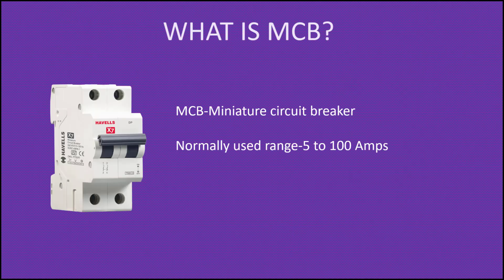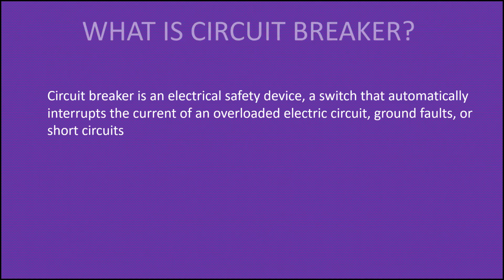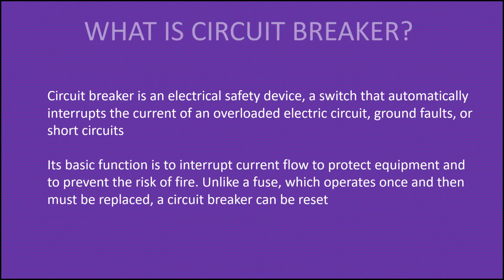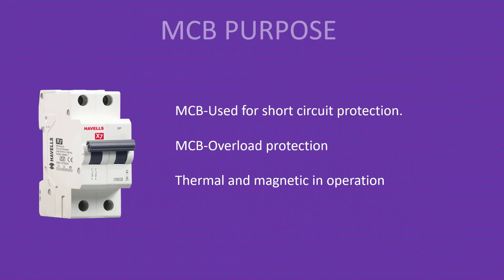What is MCB? MCB is a Miniature Circuit Breaker, normally used in the range of 5 to 100 amps. A circuit breaker is an electrical safety device that can protect the circuit or equipment from three conditions: overload, ground fault, or short circuits. Its basic function is to protect equipment, prevent fire, and avoid loss of life. MCB is used for short circuit protection and overload protection, and it will operate in both ways — thermal and magnetic.